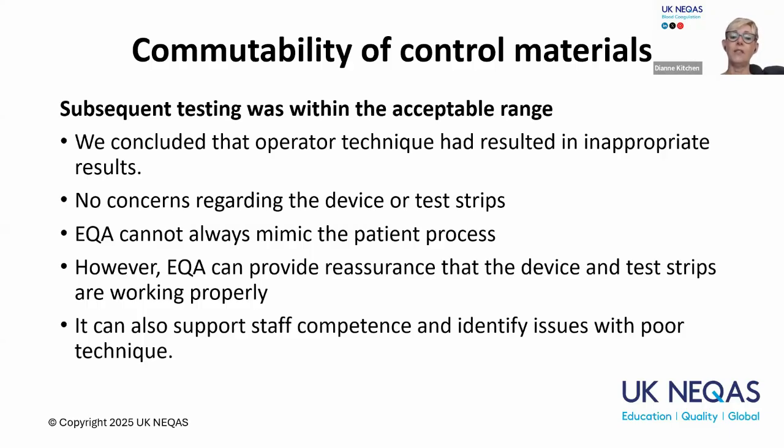But as you've seen highlighted here, if you can't follow the instructions, it shows in the results, and it can show up staff competency issues and training issues. Then the point of care teams can focus in on that operator, give them the support and the tools to make sure that going forward we are just checking the devices and not their ability to actually perform the test.